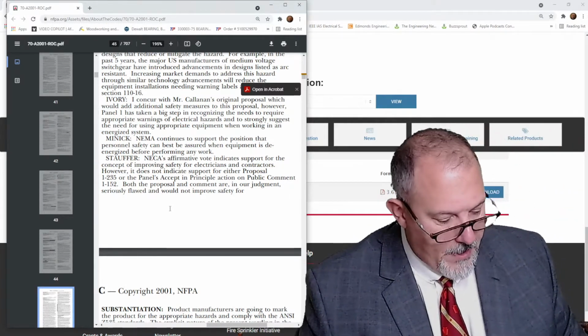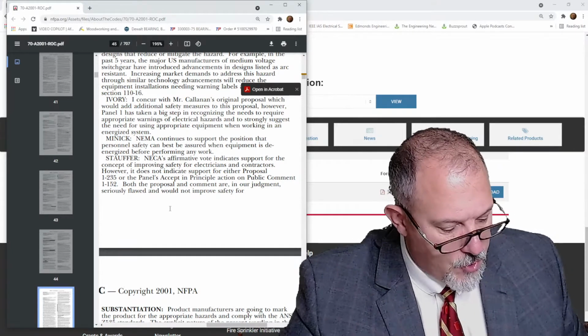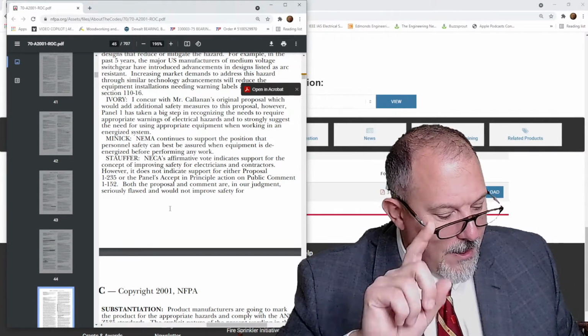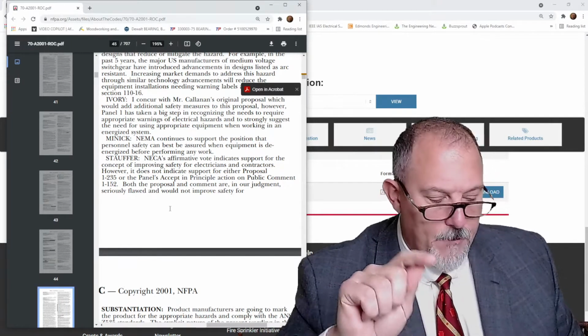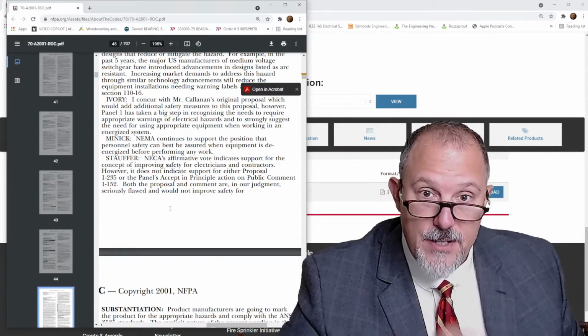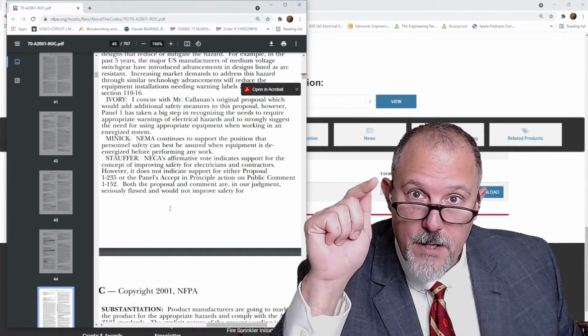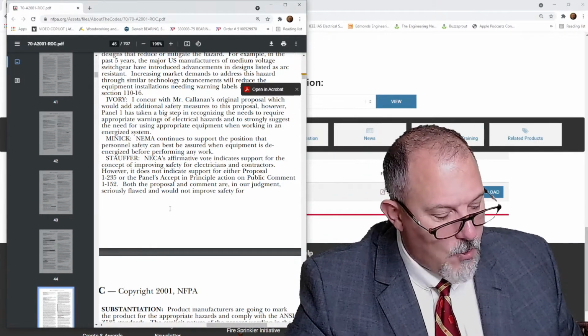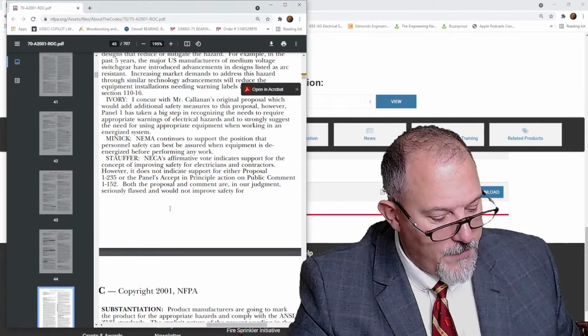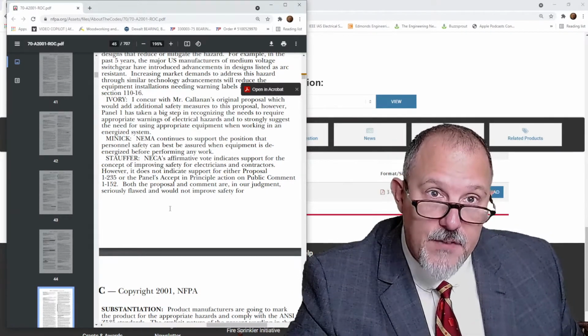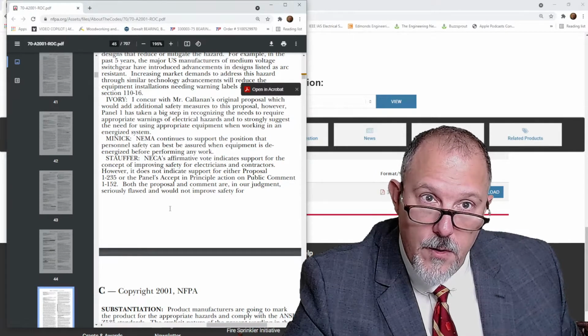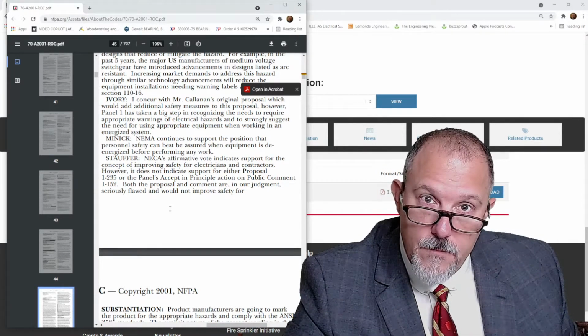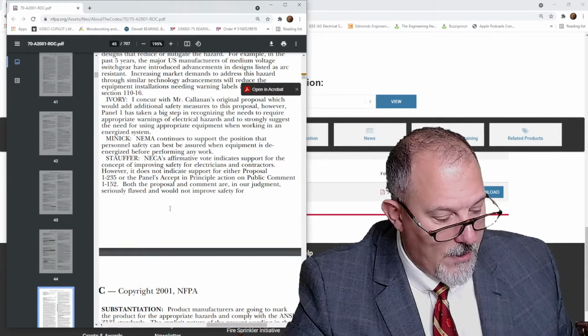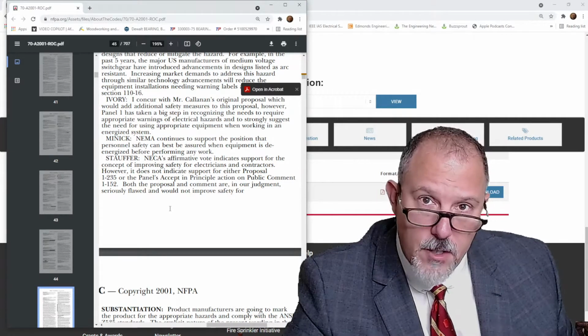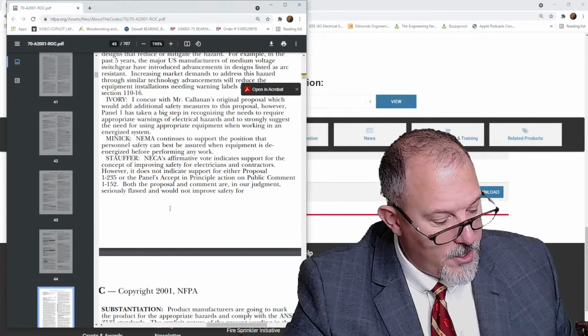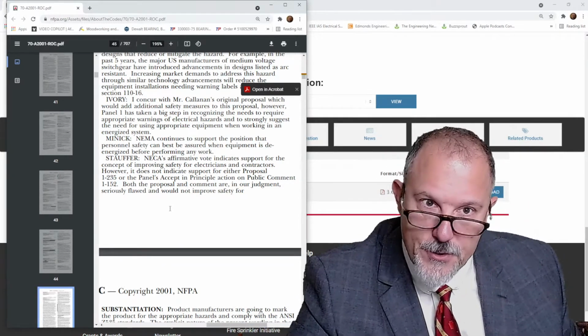It says switchboards, panel boards, industrial control panels, and motor control centers that are in other than dwelling occupancies and are likely to require examination, adjustment, servicing, or maintenance while energized. That's a significant piece of the puzzle. Remember, it says are likely to require examination, adjustment, servicing, or maintenance while energized. If something can be shown that is not likely to require servicing while energized, it would not have to be marked to warn the qualified person of a potential electrical arc flash hazard.